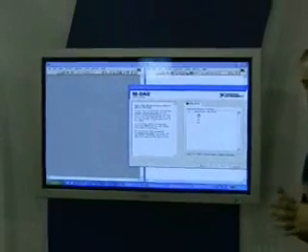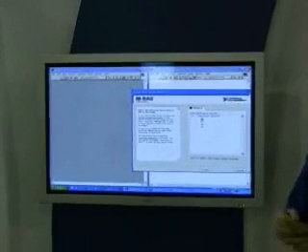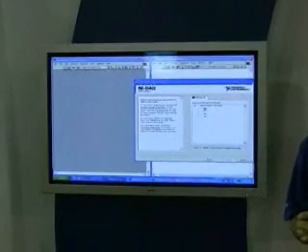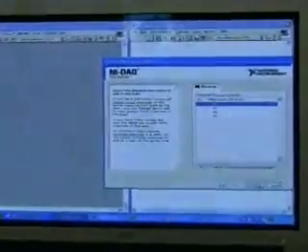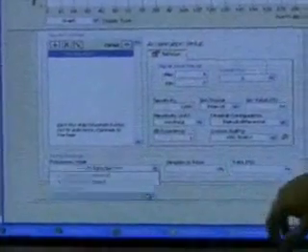You can see it detects 4 channels that I can acquire from corresponding to the 4 channels on my CompactDAQ system. We'll go ahead and select channel 0, click finish, and here I can configure things, my acquisition rate, the excitation, the voltage input, etc. All I'm going to do is change my acquisition rate to continuous and then set it to 50 kilosamples per second to pull it into my measurement system. Let's type that 50K in, hit OK here.